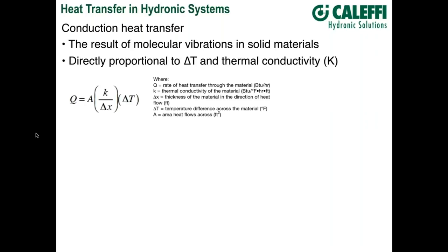That's true for conduction, convection, and radiation — you need a temperature difference to move thermal energy. The delta X in the equation is the thickness of the material. The thicker it is, the slower the rate of heat transfer. For example, an 8-inch-thick batt of fiberglass insulation versus a 4-inch-thick batt gives you twice the thickness and, in theory, half the heat transfer rate by conduction.